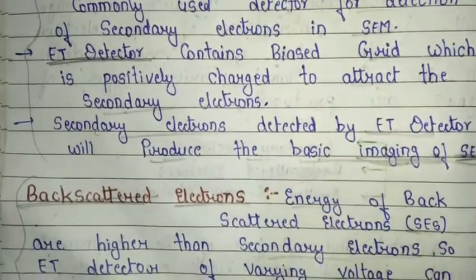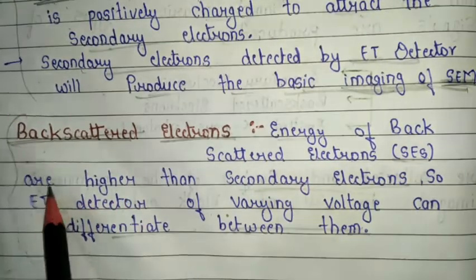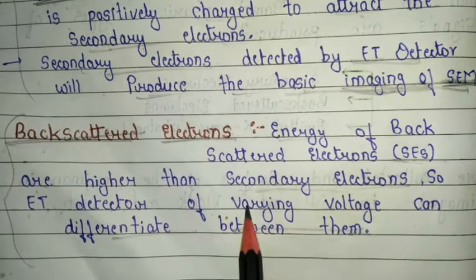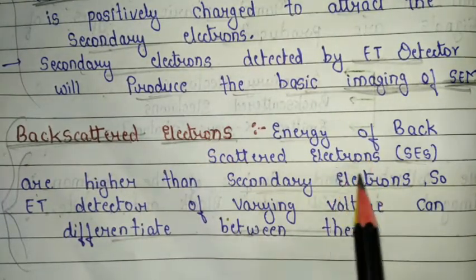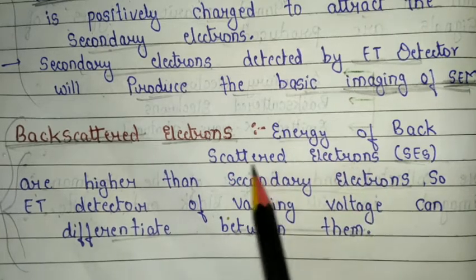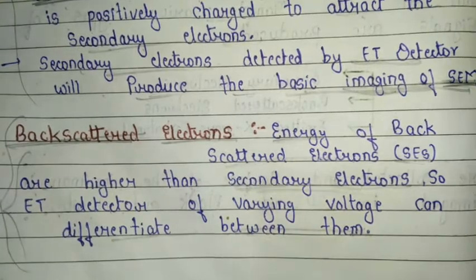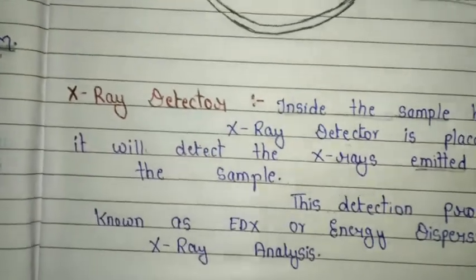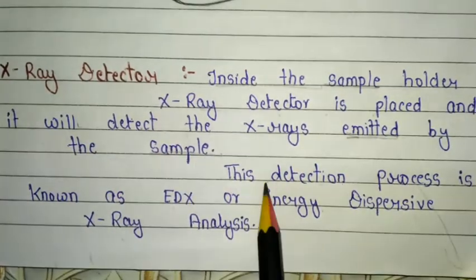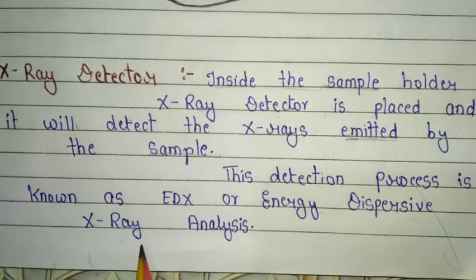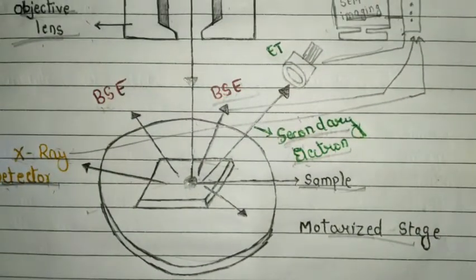The second detection in SEM is backscattered electrons, which is one of the very important signals. The energy of backscattered electrons is higher than that of secondary electrons. An ET detector of varying voltage can differentiate between them. The third detection in SEM is X-ray detection. Inside the sample holder, an X-ray detector is placed and it detects the X-rays emitted by the sample. This detection process is known as EDX — energy dispersive X-ray analysis.